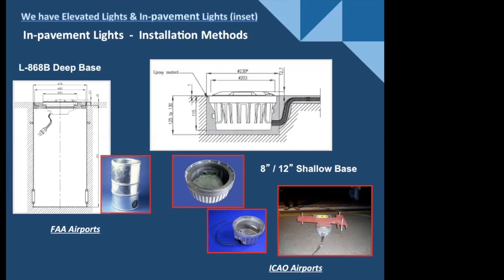Because it's dissimilar. It's not made of asphalt, it's aluminium alloy. So we've got dissimilar materials there. So what we have to do is glue this into the hole we core with some kind of suitably approved resin. But we've also got to get the electrical cable out to the light fixture. So this is quite a challenging thing to do, and there are different methods of how we get the electrical cabling to the light fixture, especially if it's a touchdown zone or a runway centerline light, which is out into the pavement, or a taxiway centerline light.